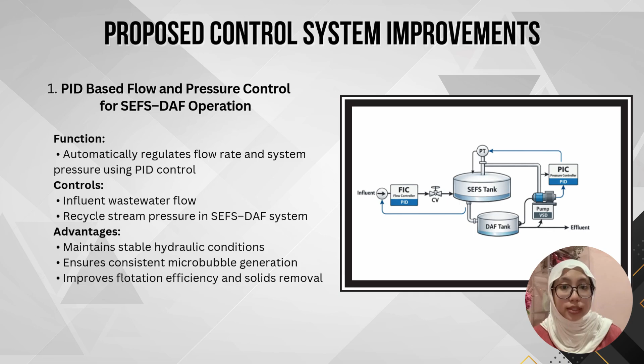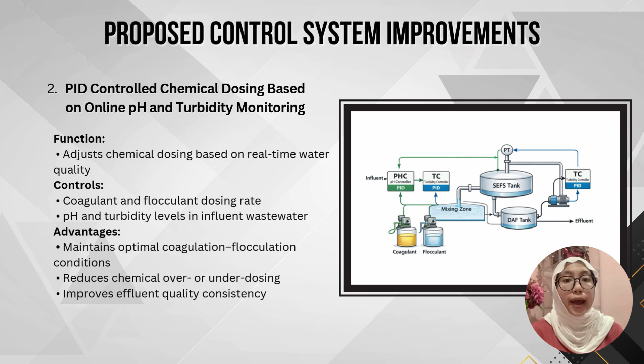Okay, next for the second improvement, PID control of chemical dosing is introduced using online pH and turbidity monitoring. The system continuously measures the wastewater pH and turbidity and automatically adjusts the coagulant and flocculant dosing rate. This ensures optimal coagulation and flocculation at all times. As a result, chemical over or under-dosing is reduced, the sludge formation becomes more stable, and effluent quality is more consistent.